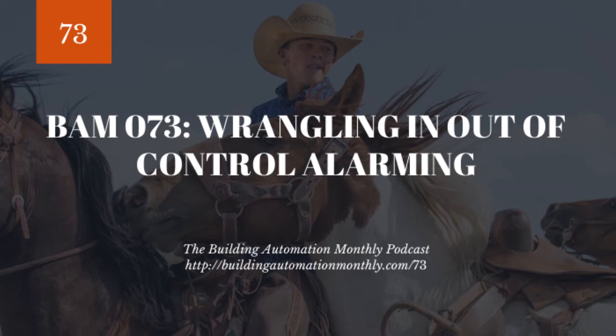Because is a filter switch the same priority as a VAV box? Is a VAV box that serves the data closet more important than a VAV box that serves maybe an open air auditorium? You have to look at the context, and that, unfortunately, is something that a lot of specifications just aren't very good at.